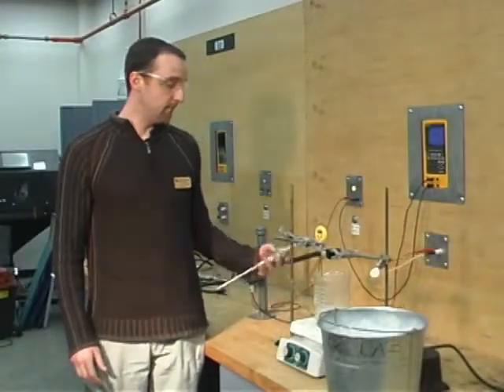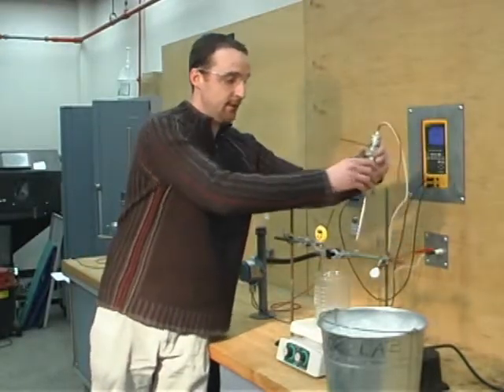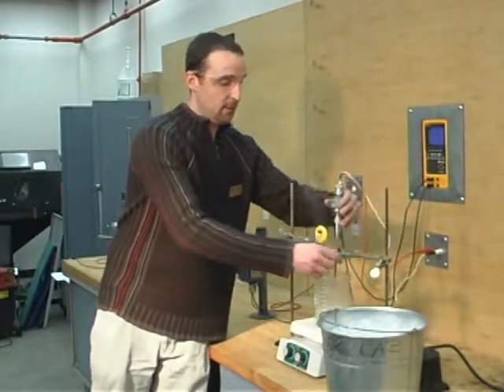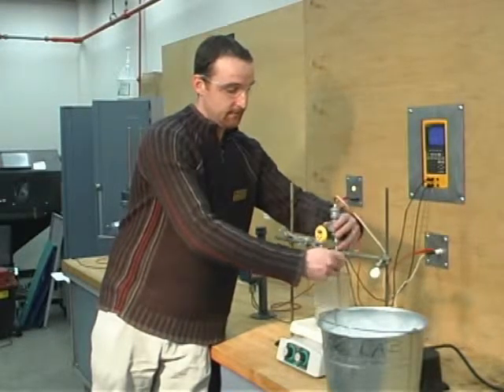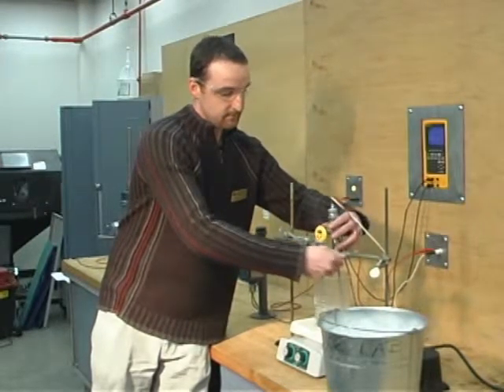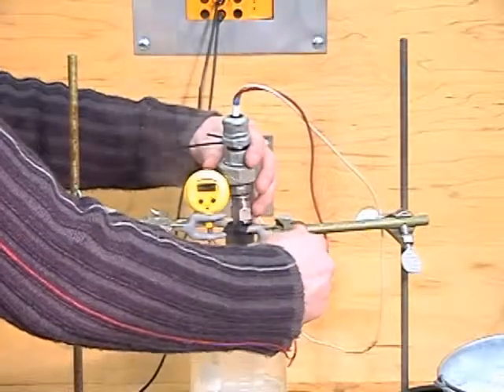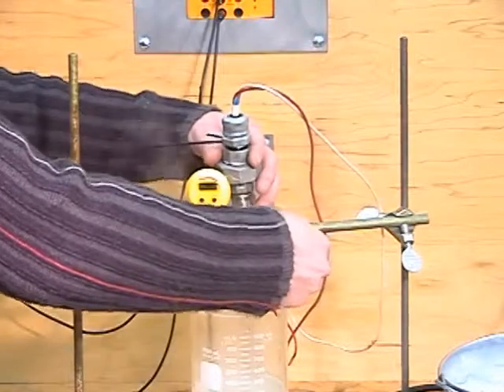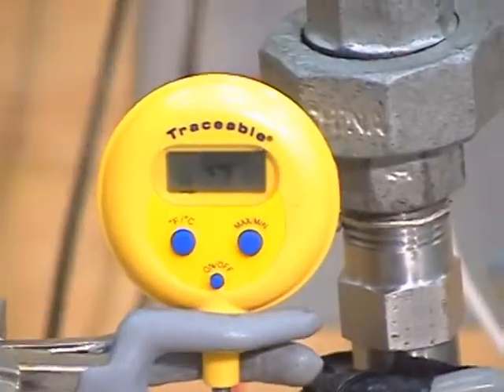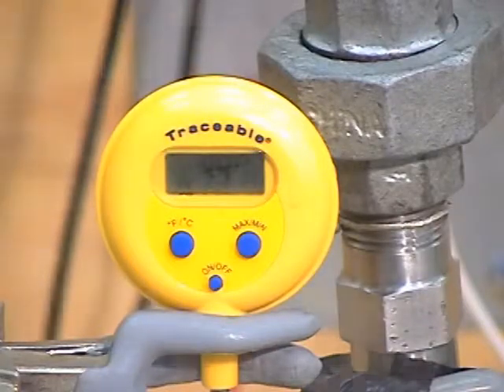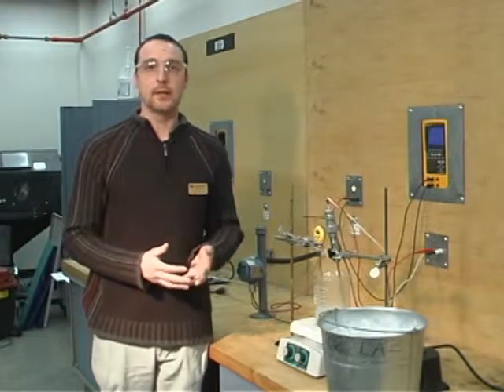Now for the first portion of our lab, we are going to insert the J-type thermocouple into our retort stand and directly into the water. We are going to take our milliamp reading, which from 0 to 100 degrees Celsius will be interpolated between 4 and 20 milliamps. 0 degrees Celsius being our 4 milliamps, and 100 degrees Celsius being our 20 milliamps.